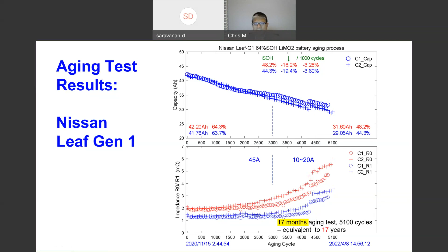Beyond 3,000 cycles, the impedance starts to increase quite dramatically. Even though the degradation from the top is still linear, the impedance does increase quite quickly. So they are still good for use in storage applications. The only attention we have to pay is that we cannot discharge or charge them at a high C rate, because that's going to increase the loss inside and speed up the degradation. So if we want to continue to use them after 3,000 cycles, roughly before 6,000 cycles, we can still charge them at a much lower rate, so they can still be used in energy storage applications.